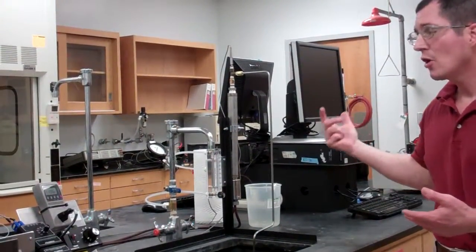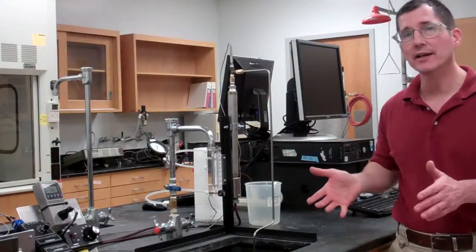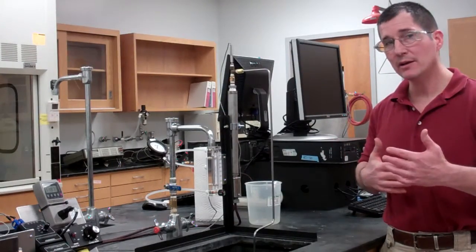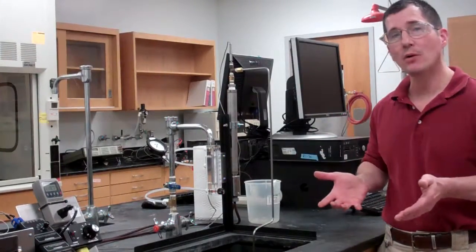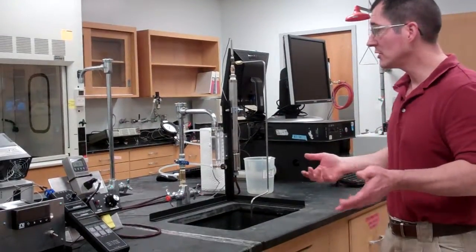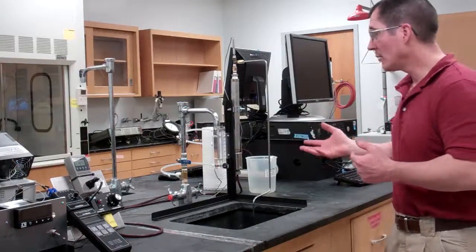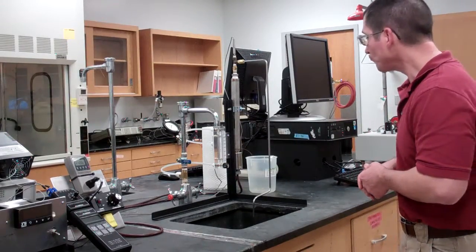What you have to understand is that with certain flow rates, you're only going to be able to control the temperature to a certain limit, because there's only so much power that the heater can put out. So you'll need to explore what your range of control is going to be with this final control element.